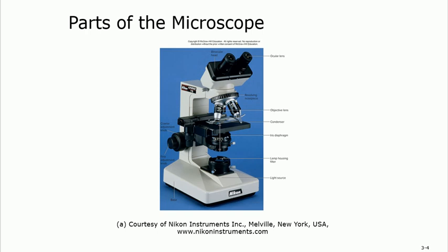And then this is the slide that you will be using for this type of microscope. This is the optic one, or the light microscope. This part here is the adjustment. The big one here is a coarse, and this is the fine one. So you do the coarse first until you get the slide close enough. You start to see a little bit, and then you do the fine adjustment so you can see the details. And then you will have an iris or diaphragm, and this diaphragm is basically controlling how much light is going to pass through and go to the specimen on that slide.